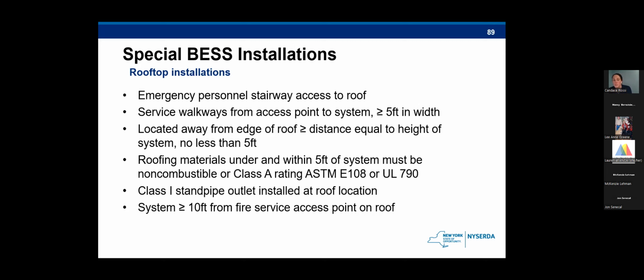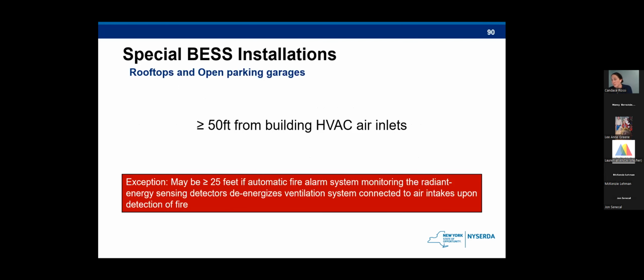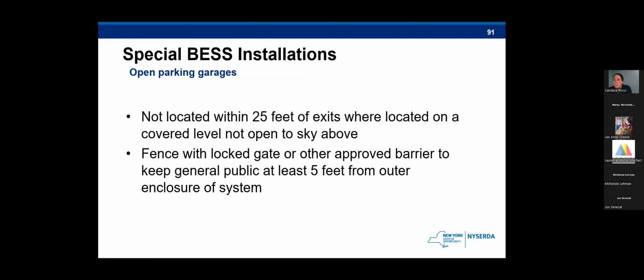So basically, for systems on the roof, you're really making sure that the system is installed safely and with enough room to give firefighters decent access if there is some sort of issue. Both rooftops and open parking garages have to be at least 50 feet from building HVAC inlets. And for open parking garages, the system cannot be located within 25 feet of exits where located on a covered level. And then you need to have a fence with a locked gate or another approved barrier to keep the general public at least 5 feet from the outer enclosure of the system.